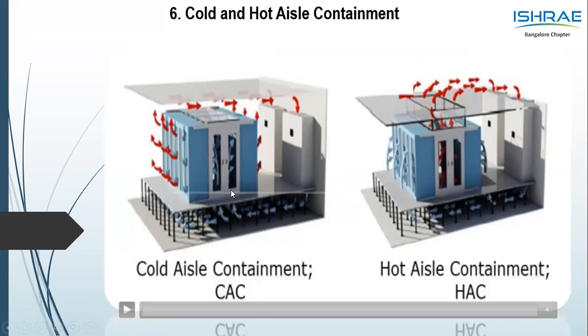And again, in a cold aisle containment, when you contain the cold air, the entire rack from the bottom to the top is maintained at a constant temperature. Not to give a comparison, but the fact of the matter remains, as long as you do a containment, it is efficient and a best practice in terms of saving operational cost and having an energy efficient data center. So on the server room, we saw the CRAC units, DX units, smaller capacity, what goes into that.